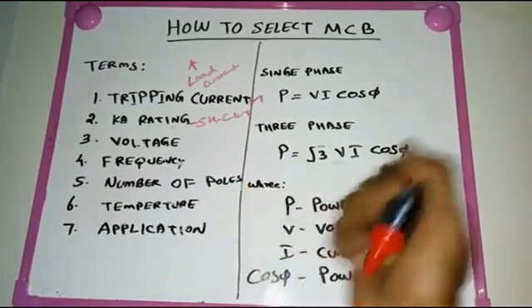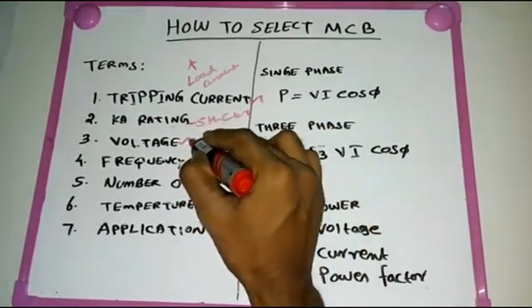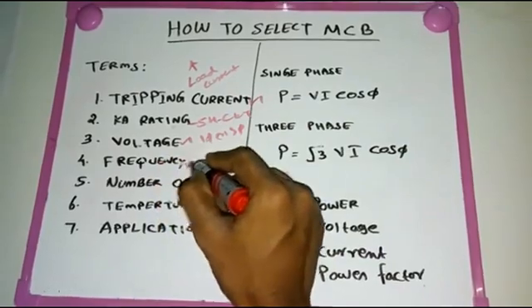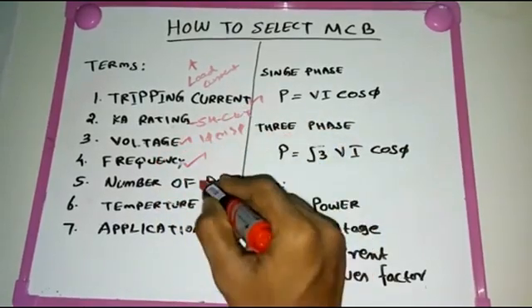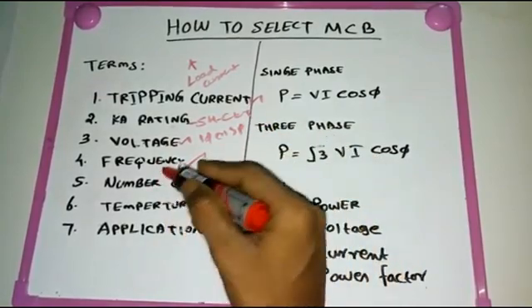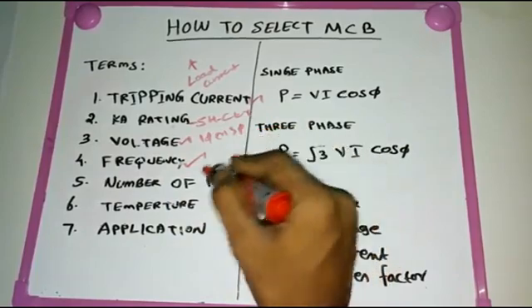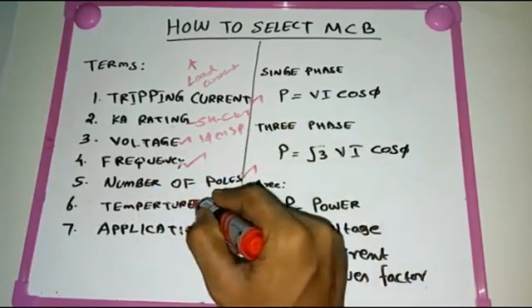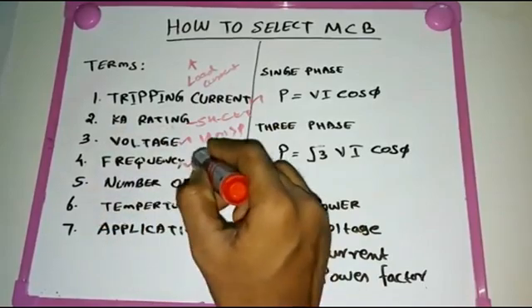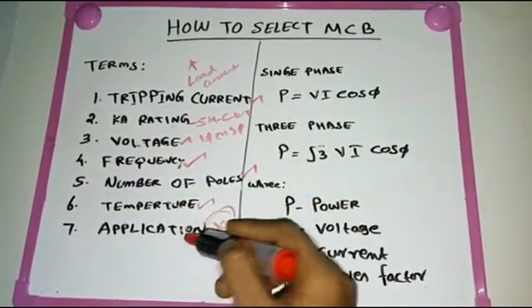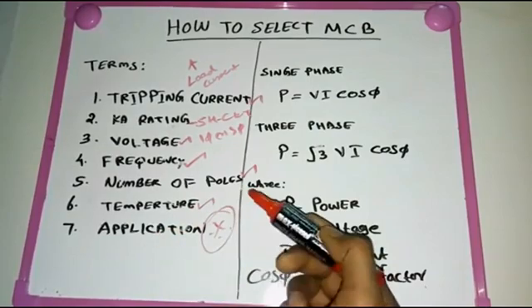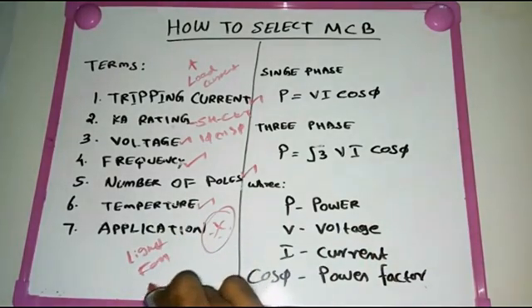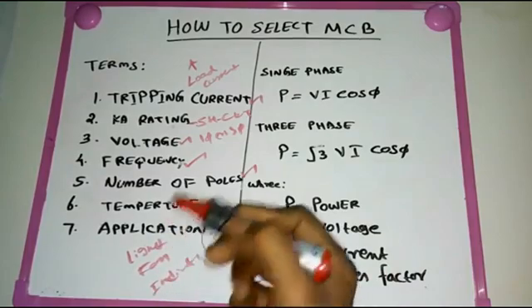Next are voltage, frequency, and number of poles, based on the phase you are using. For single phase: 230 volts. For three phase: 440 volts. Frequency is typically 50 Hz or 60 Hz depending on your location. The number of poles is based on whether you use single phase or three phase. Temperature is also important — whether you are in a cold area or hot area affects your MCB selection. The application — lighting, fan, air conditioner — is also very important.